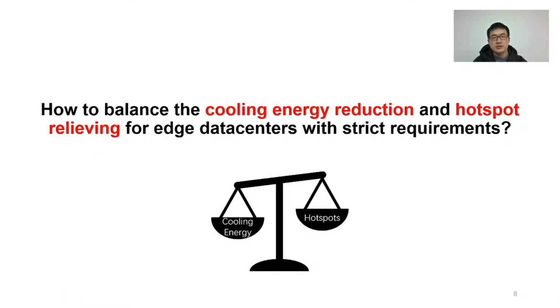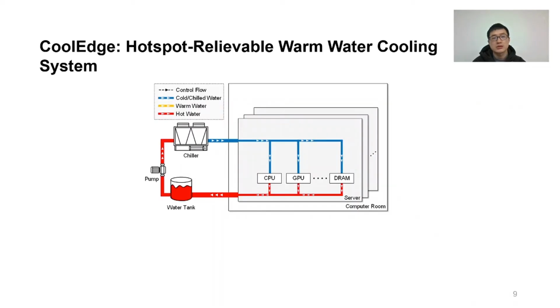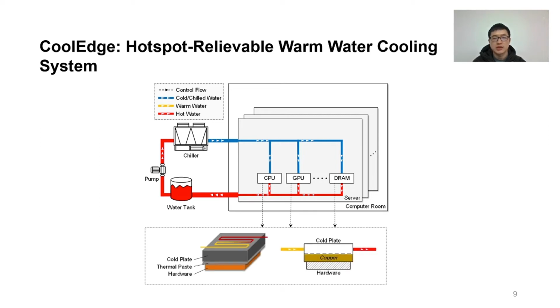Facing the strict requirements by edge datacenters, how can we relieve multiple level hotspots while saving the cooling energy? Our solution proposes a fine-grained warm water cooling system named CoolEdge to relieve multiple level hotspots with the least cooling energy. In a conventional coarse-grained water cooling system, all the hardware components share the same cooling water temperature and flow rate, and the heat is absorbed by the cooling water through copper-based cold plates.